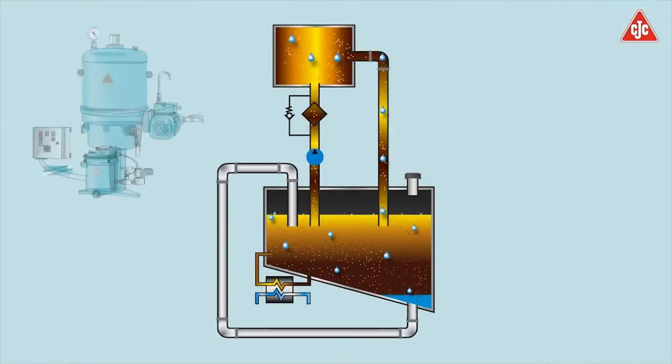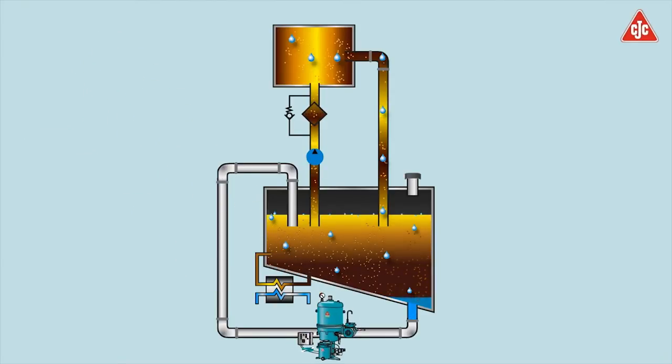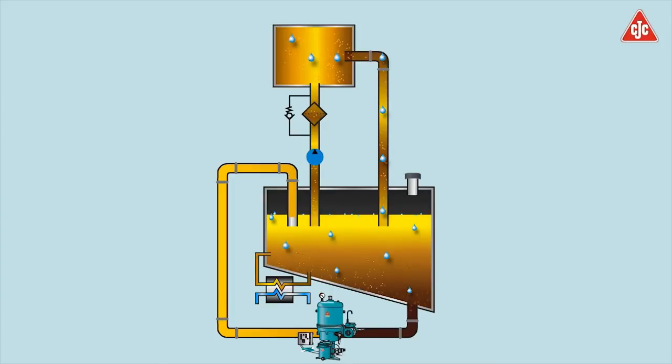A CJC filter separator is installed offline. The oil is pumped from the lowest point of the oil tank and enters the CJC filter, and the CJC inserts retain the contamination. The clean and dry oil is returned to the system and contamination will be removed continuously.